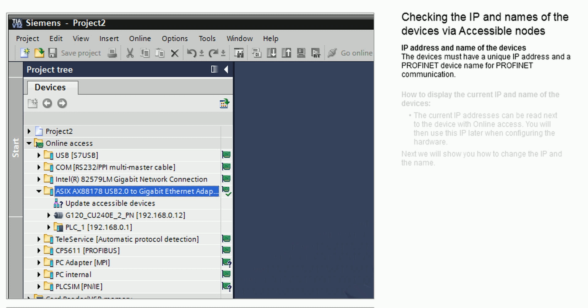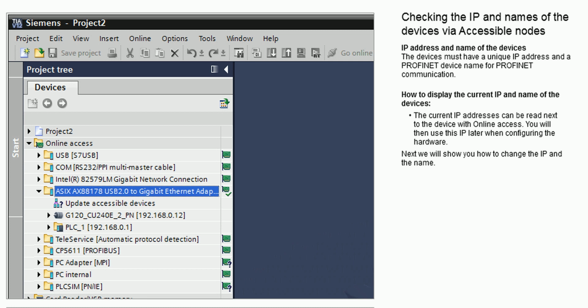IP address and name of the devices. The devices must have a unique IP address and a Profinet device name for Profinet communication. How to display the current IP and name of the devices. The current IP addresses can be read next to the device with online access. You will then use this IP later when configuring the hardware. Next, we will show you how to change the IP and the name.